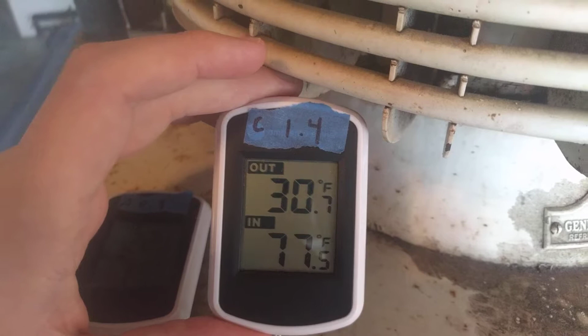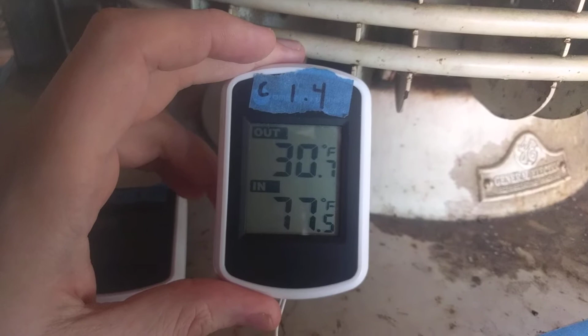So this is actually around freezing, more or less. It has brought the temperature of the water down, and it's freezing from the bottom up. So the probe at the top, we're looking for this to start dropping into the 20s, and at that point it's starting to get close to freezing. Right now it is decidedly not close to freezing, which makes sense, since we estimated it would take at least 4 hours if this thing ran continuously.